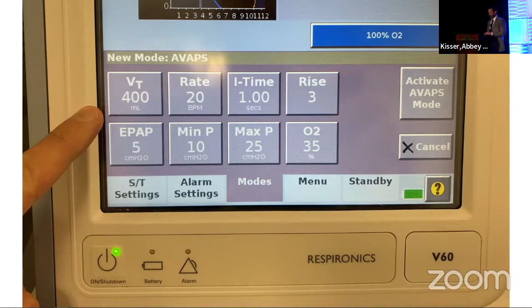Now, one of the things I always recommend when you set somebody on AVAPS is to just stay at the bedside and hold on for a little bit, because it takes a while to work. The machine is actually trying to determine what the airway pressures of the patient are and how much pressure it's going to need to give the patient to generate said tidal volume. I went over the owner's manual these past couple of days, trying to figure out if there is something else about AVAPS I need to cover. And I ran into something pretty funny. This is not meant for you to read, but it says, during AVAPS setup, there may be a period of time before target tidal volume is achieved. I found that quite redeeming. I was like, okay, it doesn't just happen to me. It happens to everybody, and it's on the manufacturer's listing.